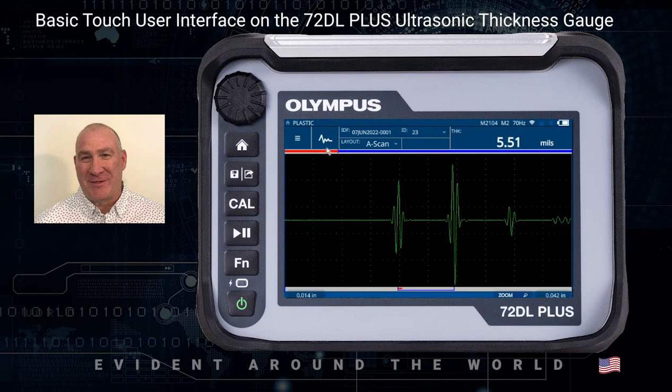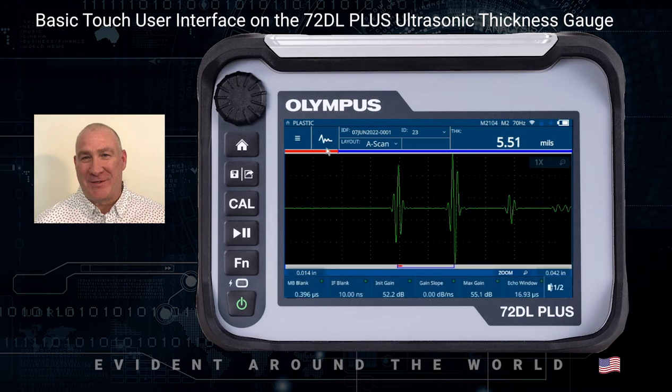Moving towards the right, the next control is the Wave Adjust. There are currently transducer parameters for the application called plastic that I recalled. When I press the Wave Adjust key, it's going to bring up the actual transducer parameters — things like main bang blank, interface blank, initial gain, max gain, and slope. You'll also notice on the far right-hand side it says one of two. There's a second line of controls that control things like the polarity of the echoes, either positive or negative. I can switch back and forth between line one and line two by clicking the control in the bottom right-hand corner.